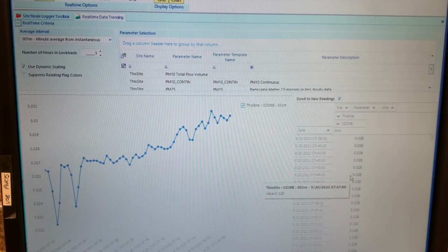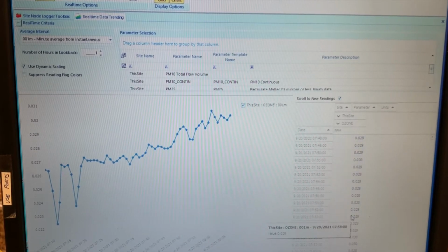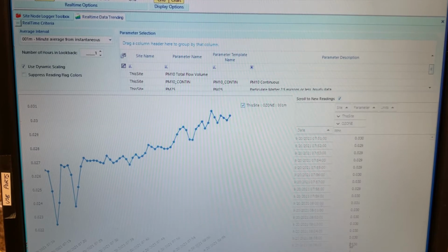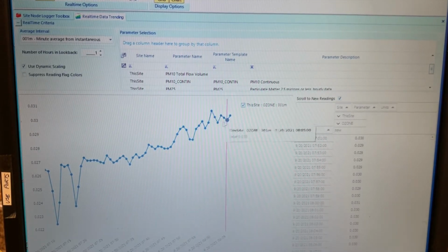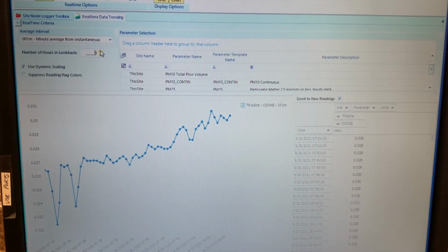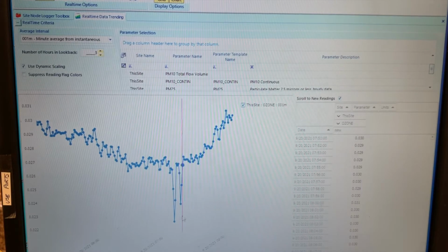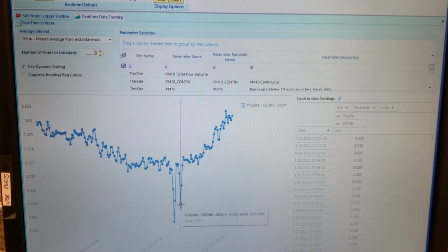The software polls each instrument on the network at a regular interval. Once polled, that data is averaged over the course of 1 minute and stored. After 60 1-minute intervals, the software then averages an hourly value. It is this value that is often used for comparison purposes to that pollutant's NAAQS. All this data now exists on the site data logger, waiting to be transmitted to the DEQ Central Server for analysis.